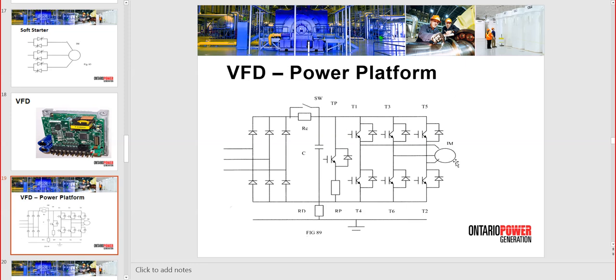So this is the schematic, the power side of a VFD. You have the rectifier. If you don't specify anything, you're going to get a VFD with diodes. That is your rectifier. And then on the DC bus, you see the capacitor and the charging resistor. Once the capacitor gets to 90% of the full voltage, you will close that switch, and it will charge faster the last 10% of the capacitor, because you cannot close the switch before. If you don't have that charging resistor, the inrush current will blow up the diodes or the fuses that protect the diodes in front. So you need to have a charging resistor and bypass the resistor whenever you are almost at the full voltage.